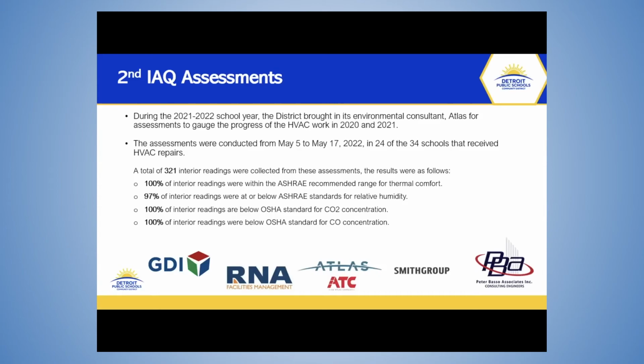We conducted assessments in 24 of those 34 buildings. A total of 321 interior readings were collected, and 100% of the readings were within ASHRAE standards for temperature, 97% were within or below ASHRAE standards for relative humidity, and we achieved 100% on both CO2 and CO with those readings. For the 97%, we had one school that had some issues with some coils. Those have since been repaired. So hopefully when we get these tested again, we'll achieve 100% for all of those ratings.